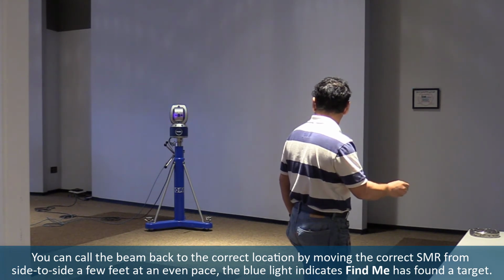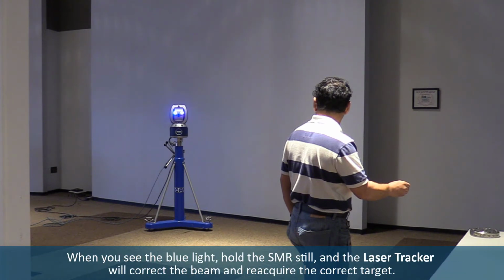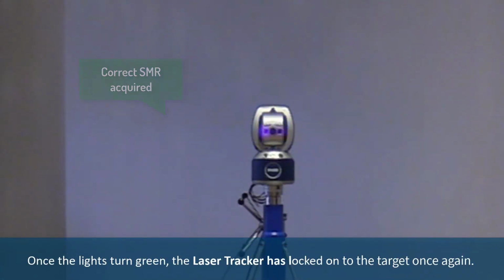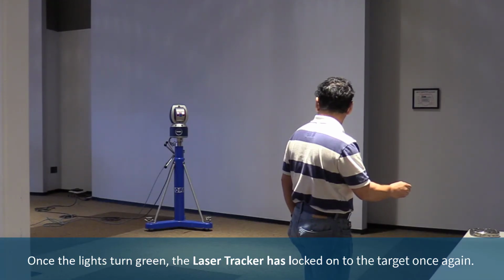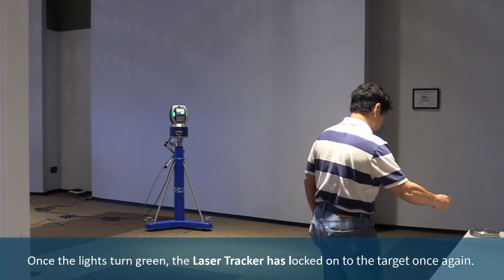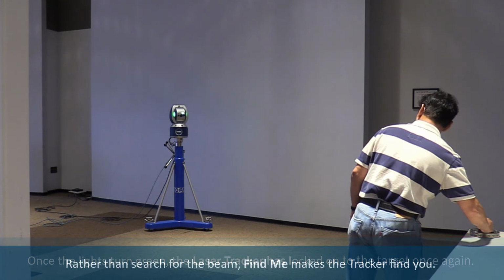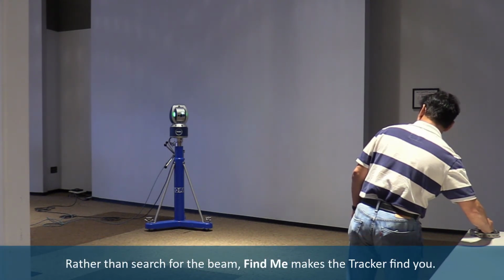The blue light indicates FindMe has found a target. When you see the blue light, hold the SMR still and the laser tracker will correct the beam and reacquire the correct target. Once the lights turn green, the laser tracker has locked onto the target once again. Rather than search for the beam, FindMe makes the tracker find you.